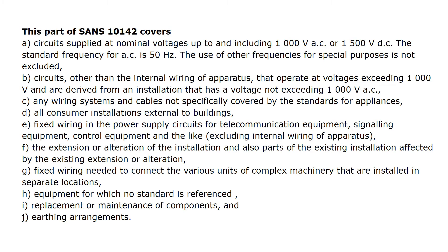Section 1.2: Aspects Covered by this part of SANS 10142. This part covers: A. Circuits supplied at nominal voltages up to and including 1000 V AC or 1500 V DC. The standard frequency for AC is 50 Hz. The use of other frequencies for special purposes is not excluded. B. Circuits other than the internal wiring of apparatus that operate at voltages exceeding 1000 V and are derived from an installation that has a voltage not exceeding 1000 V AC.